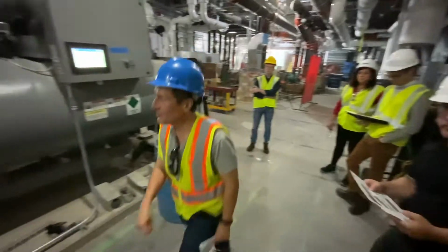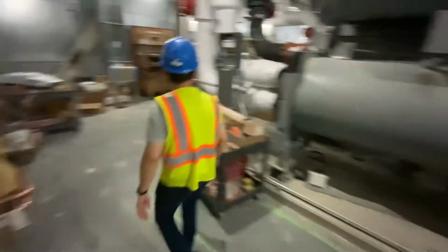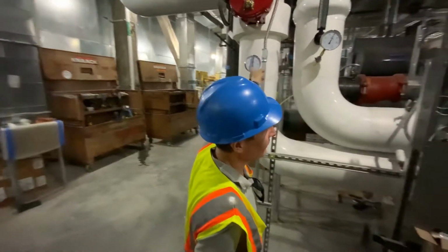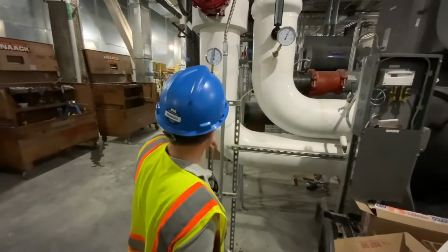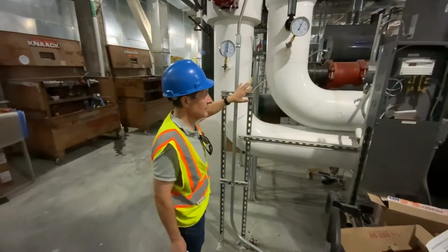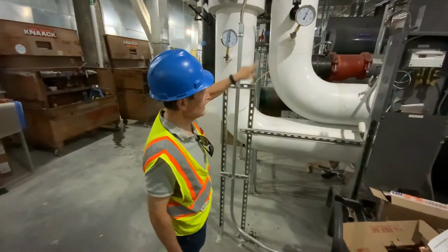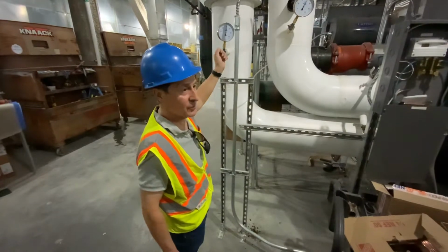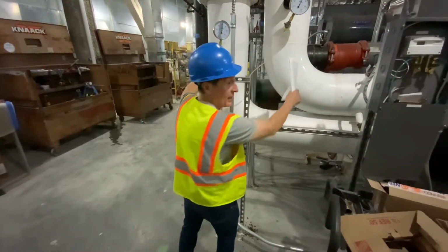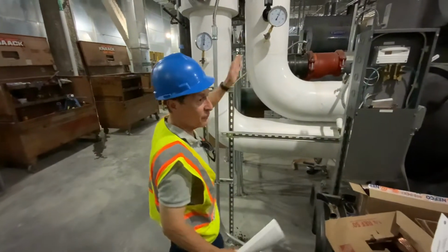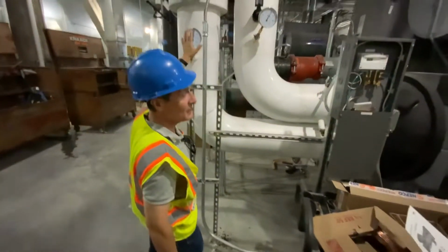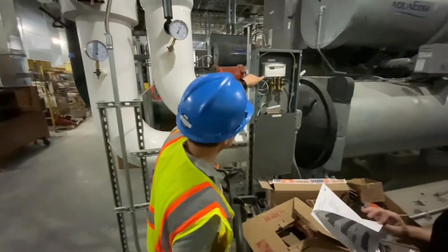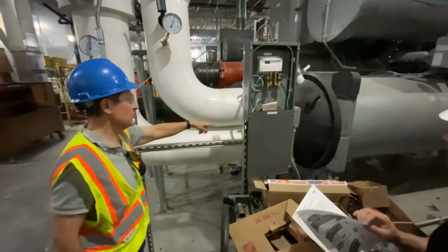So for example, you can come down here and you can look at the pressure gauges and you can see pressure differential here, okay? Obviously these aren't the most accurate to look at because they're individually sent, so if one is off, you're not comparing two pressures directly, you're comparing them individually. So on top of that, to be more safe for the chiller, they're using pressure transducers right here. They're measuring the pressure differential.